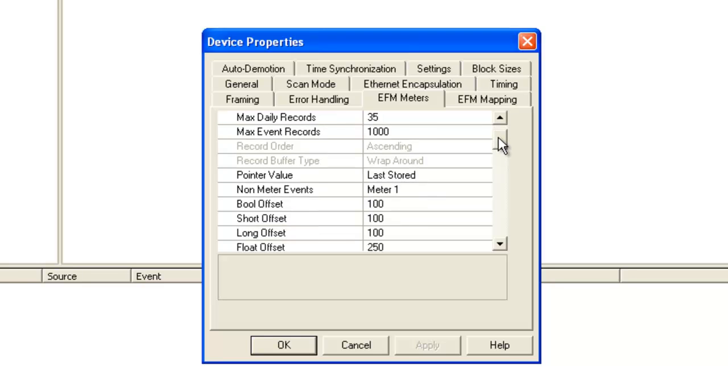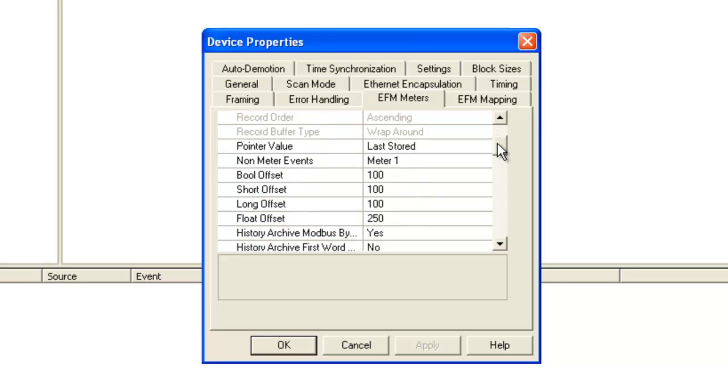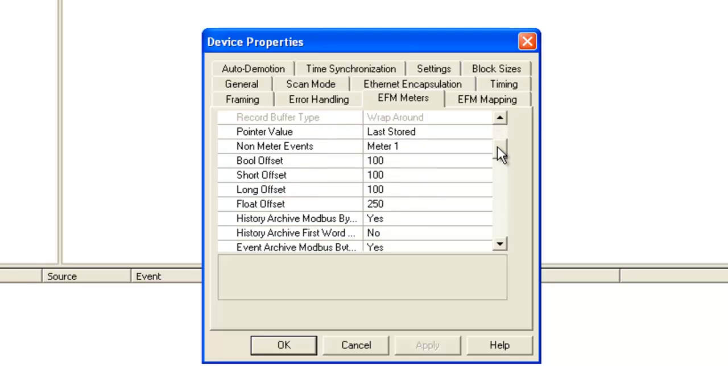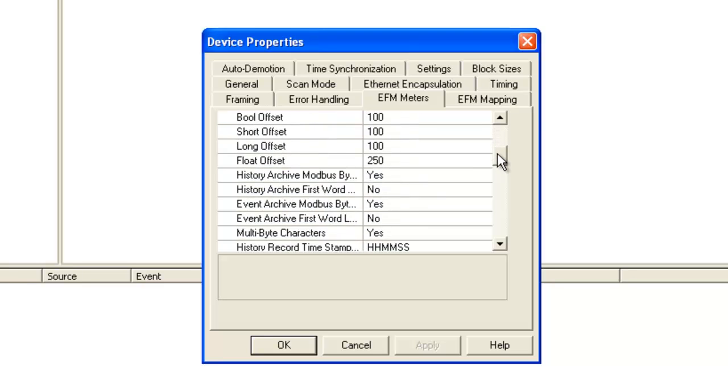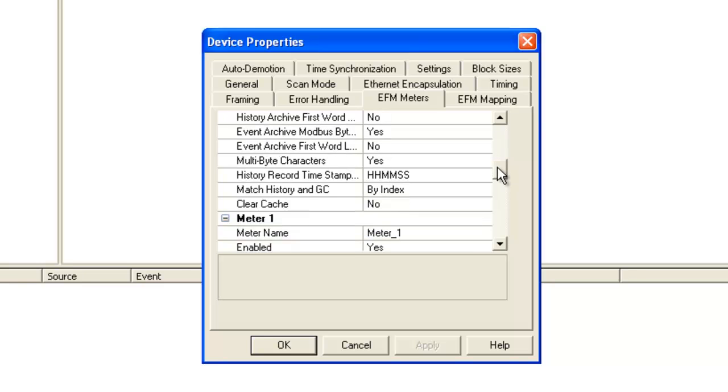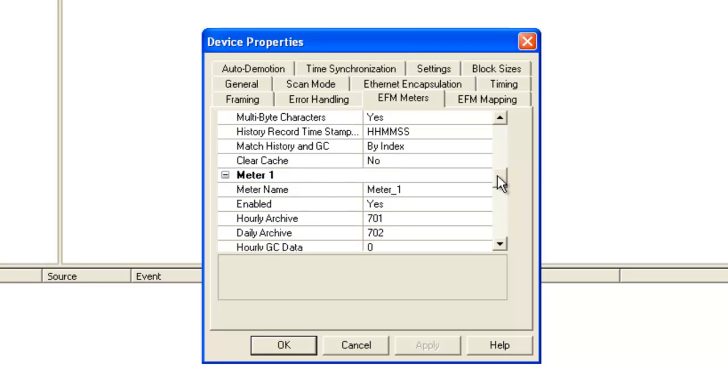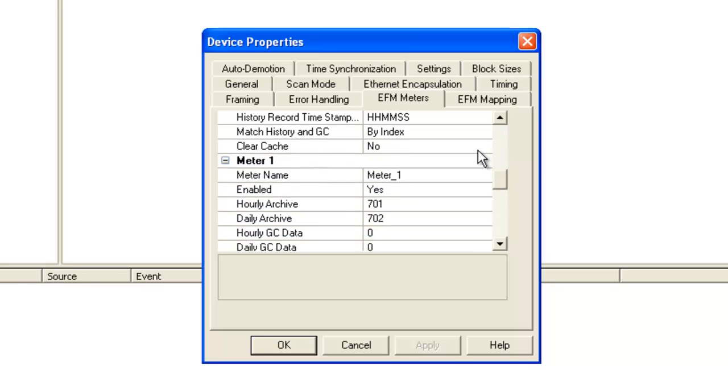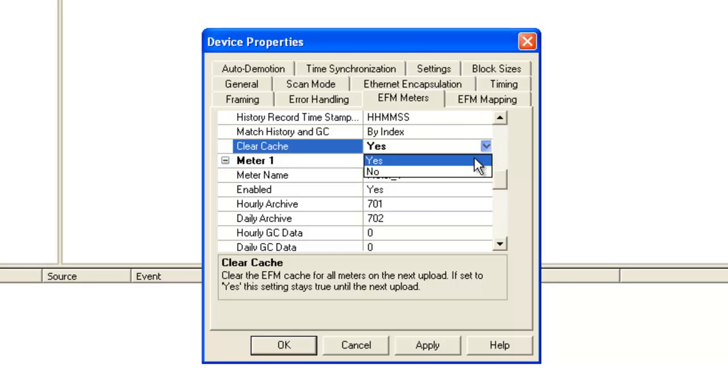A lot of these attributes are detailed in the help file, so I won't describe what they are here. More important feature is this clear cache option. The driver will cache data from the device, so it only requests data once. If you need to re-request data from the device, you would set this to yes, and that would occur on the next poll.